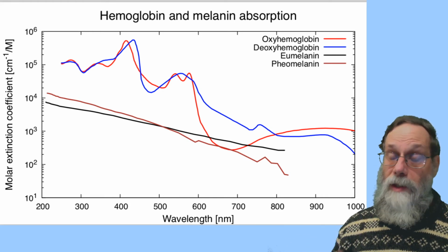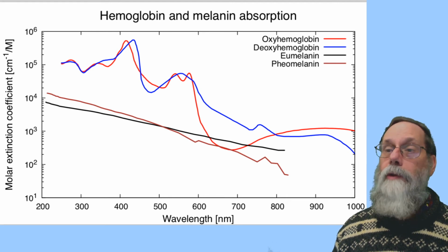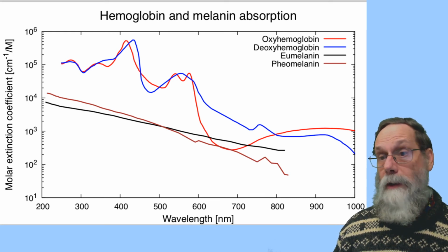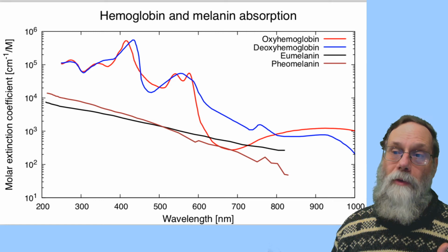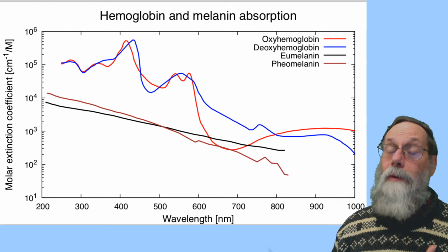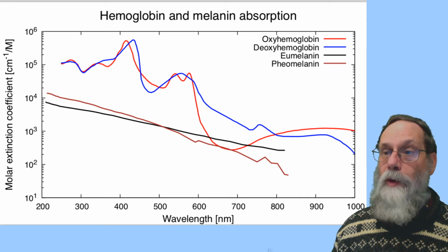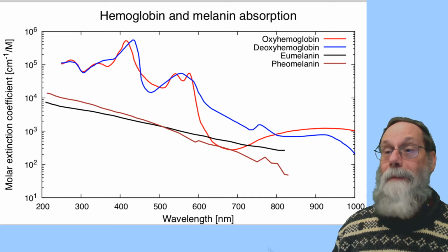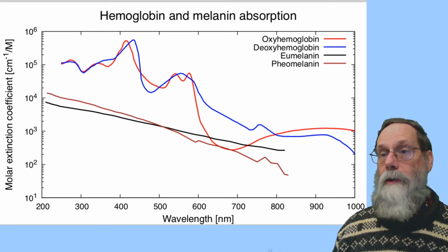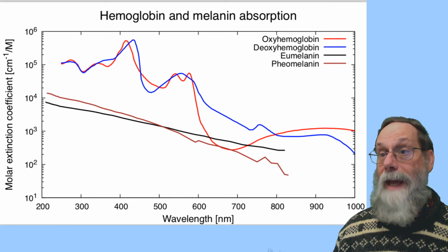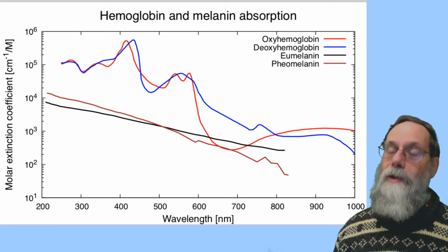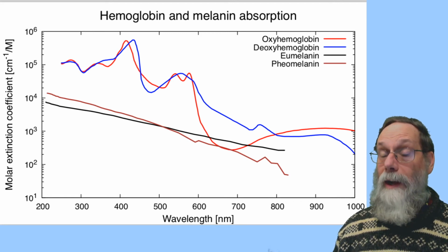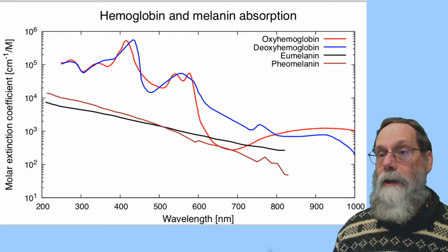But when you're doing the cis illumination for something like a smartwatch, you need to have backscatter. And the trouble is you get much more backscatter at the blue end of the spectrum than at the infrared end of the spectrum. So you have sort of this tension that you would like to ignore the absorption of things in the skin, but you need backscatter in order to be able to see light coming back from the blood vessels. And so you need something that'll penetrate sort of the right depth into the body so that it goes through the skin, the subcutaneous fat, and gets to the blood vessels, but scatters back enough from the blood vessels that you can actually see the signal.